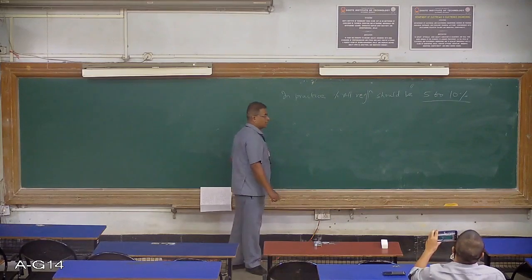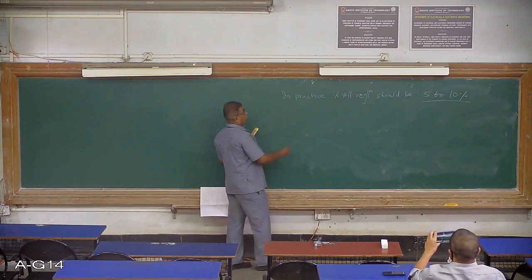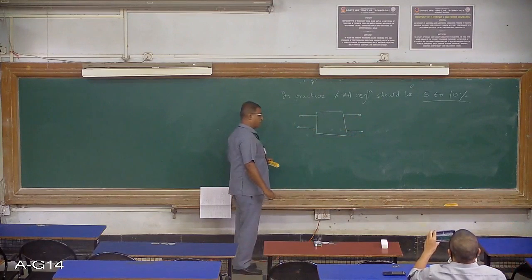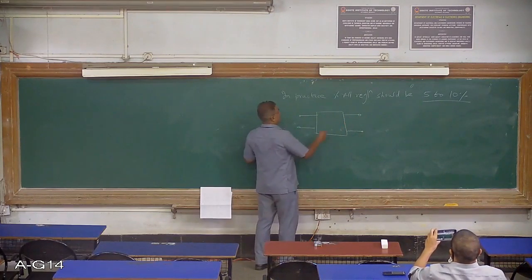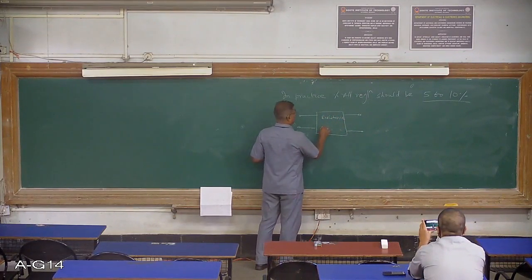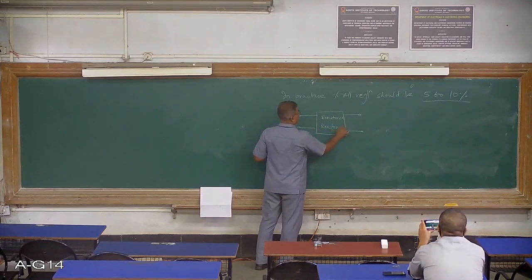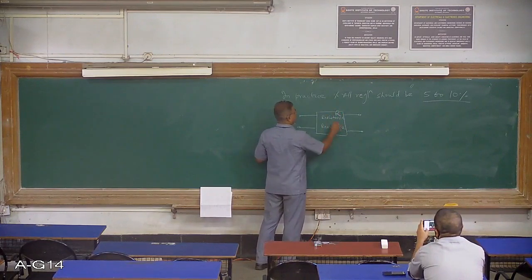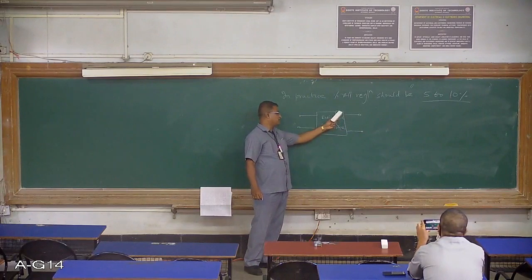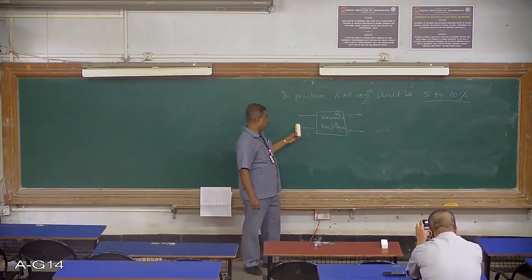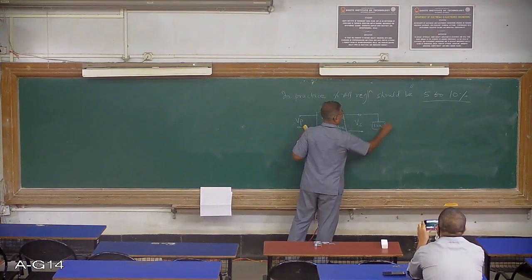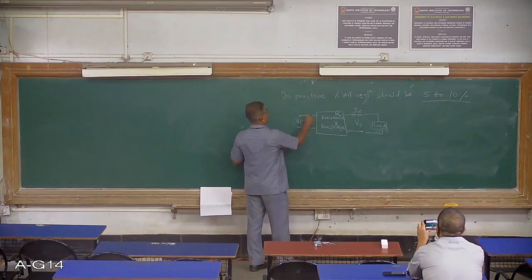It is worthwhile to know why this voltage regulation occurs. This transformer is an electromagnetic machine. It has primary winding and secondary winding, so therefore there will be primary resistance. There is resistance for the primary winding and secondary winding. There is leakage reactance for primary winding and secondary winding. Resistance is R and leakage reactance let us indicate by X or XL. So there are two parameters in primary and secondary winding, that is resistance and inductive reactance. Whenever the transformer is loaded, supply is given, secondary voltage appears, load is connected, then you will find the flow of current, secondary current IS and primary current IP.